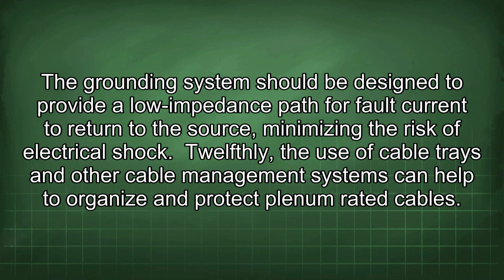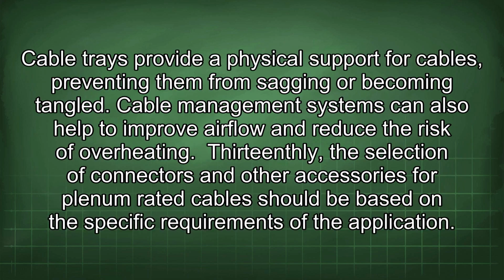The grounding system should be designed to provide a low impedance path for fault current to return to the source, minimizing the risk of electrical shock. 12thly, the use of cable trays and other cable management systems can help to organize and protect Plenum-rated cables. Cable trays provide a physical support for cables, preventing them from sagging or becoming tangled. Cable management systems can also help to improve airflow and reduce the risk of overheating.